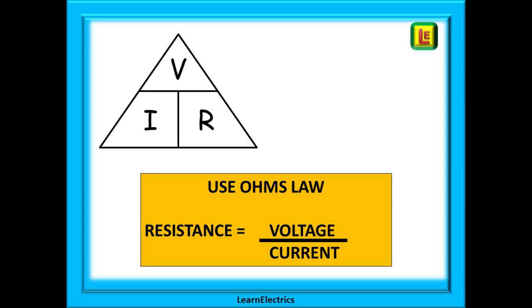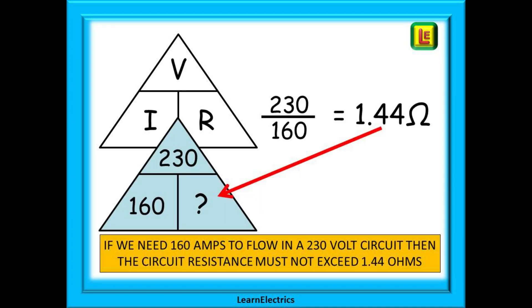A little bit of maths now. Ohm's law tells us that the resistance of a circuit equals the voltage divided by the current. We have shown here the familiar Ohm's law triangle. Inserting the two numbers that we know, we have 230V over 160A. We always use the nominal voltage for these calculations and not the actual measured voltage — it is the standard figure quoted in tables and books. So 230V divided by 160A gives us 1.44 ohms. If the resistance is equal to or less than 1.44 ohms then at least 160A of fault current will flow and the circuit will disconnect in 0.4 seconds or less.